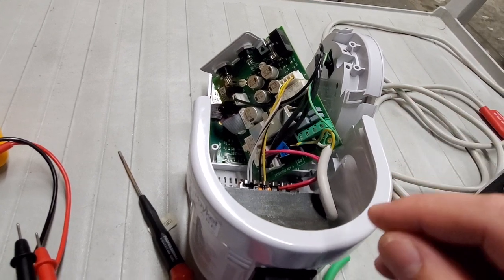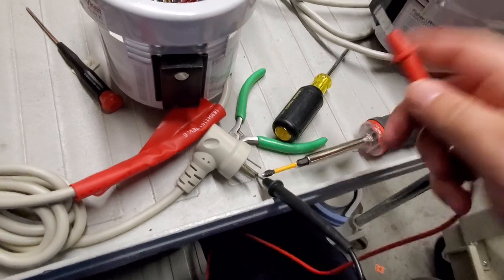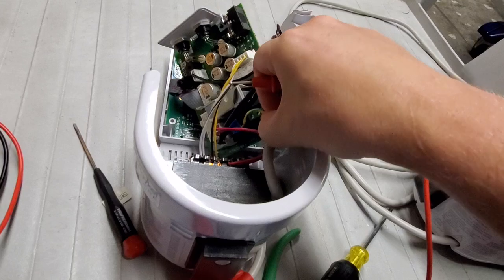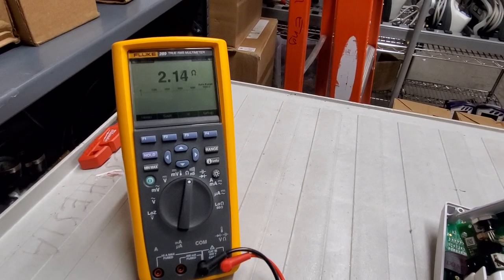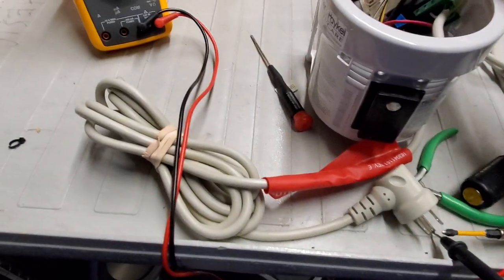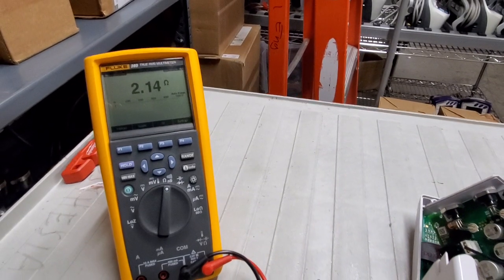I'm just going to show you that if I put one lead down here and the other lead, I'm going to grab and stick directly on the other end of the power cord — I got two ohms. This power cord has never been undone. As far as I can tell, there are no crimps or anything that would damage it. Looks like a perfectly good power cord, but this is how it is on the inside.